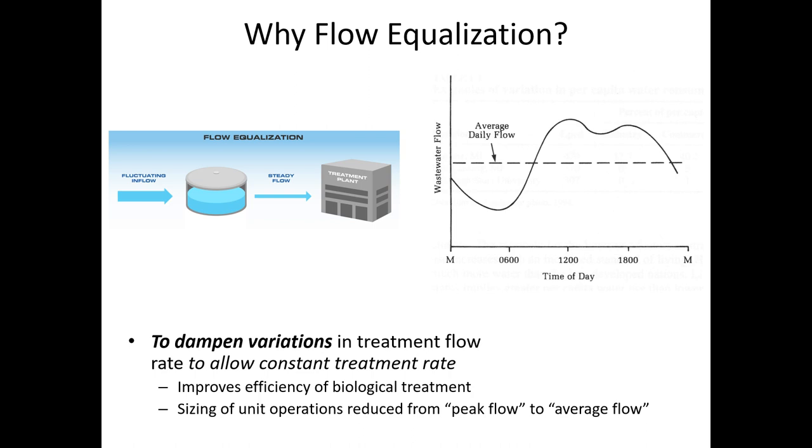Because of these wide variations in water that comes through the treatment plant at the beginning of the day versus at the end of the day, we have a storage tank for the wastewater so that you can draw from the storage tank at night and add to it during the day. Anytime the inflow is greater than the average daily capacity of the treatment plant, you'd be adding to the tank, and anytime at night when the flow coming into the treatment plant is lower, you'd draw from it.